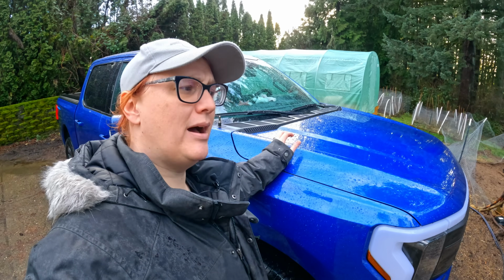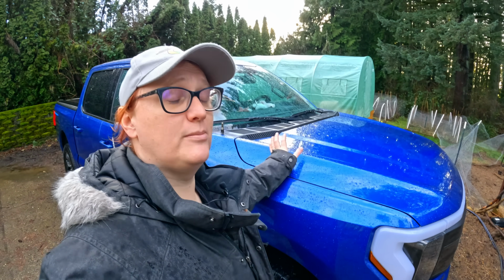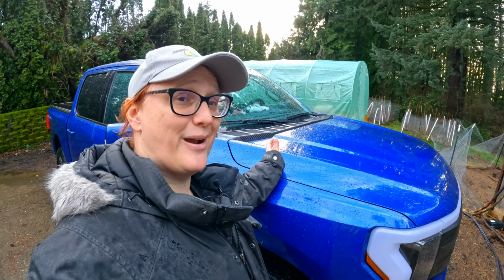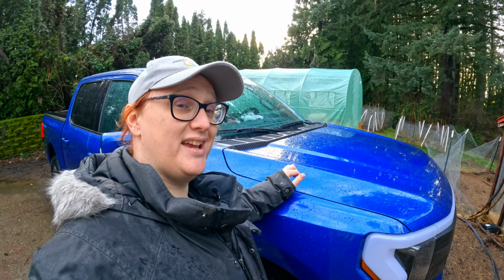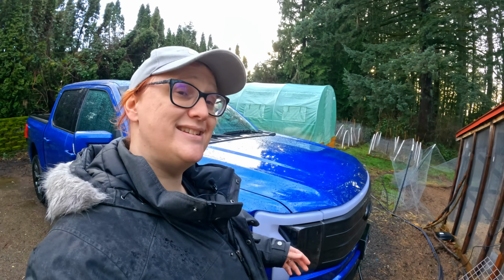And we actually ran a test shortly after I'd turned everything back on, and as luck would have it, during the test, about half an hour to an hour in, I got a message on my smartphone from our local utility saying your power is out. Don't worry, we're working on it. And the truck was powering the house, and it continued to power the house throughout the power cut. I actually turned on all the breakers again so that when the power did come back on, it just automatically switched over, and it did, and it was fine.